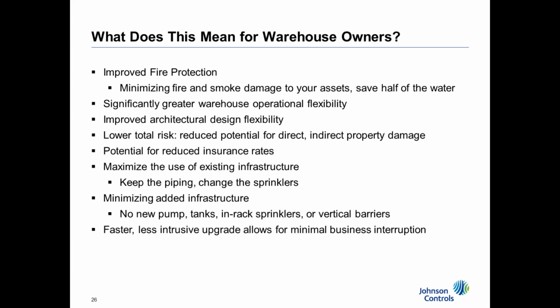You don't need to worry about in-rack sprinklers. A system like this allows you to store increasingly complicated commodities. You're able to expand your product packaging options. So you're really future-proofing your warehouse in a way. And there are no barriers required as well. There's more flexibility with your racks, so from an architecture design standpoint, there's more flexibility there. And what you get, of course, is a lower total risk, and a reduced potential for direct and indirect property damage, as you can see from some of those fire tests we've conducted. The bottom line, and this is what I'd really like for you to take away from this, is that integrated solutions like the electronic sprinkler system allow us to deliver fire protection compliance while maximizing the operational flexibility in a warehouse.